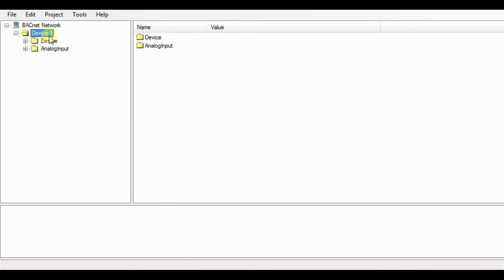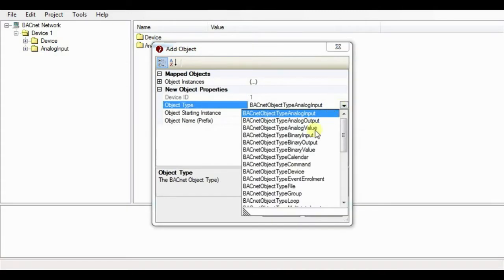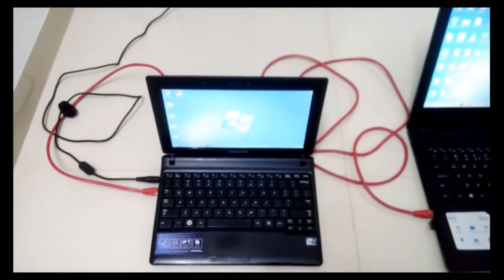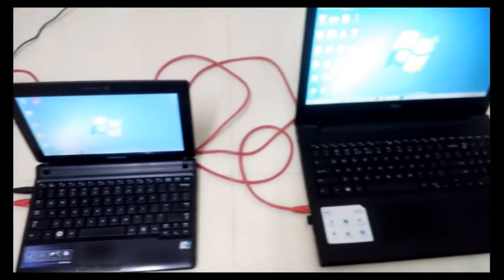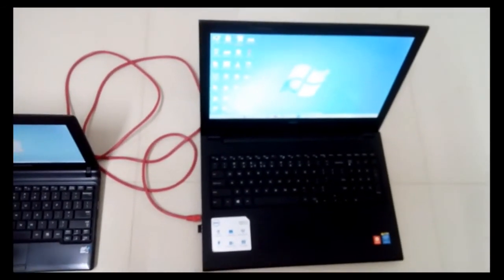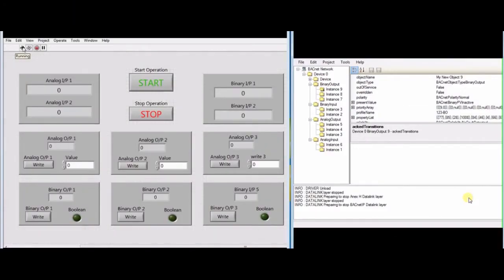You can choose any object as per your requirement. In our case, we will perform the read operation and also the write operation. The actual connection between the BACnet simulator and LabVIEW VI will look like this — the BACnet simulator is running on a small PC and LabVIEW on the big one, and both are connected with a red ethernet cable. After pressing the run button, the VI will successfully fetch the different objects from the simulated BACnet device running on a different computer.